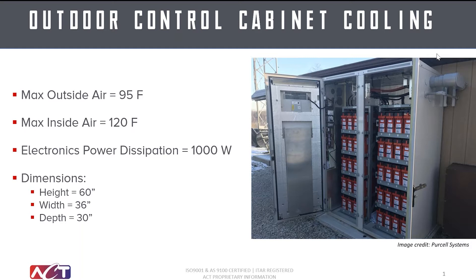The boundary conditions you see on the left are potential environmental requirements you might see from a customer, dictated by the components in your system and where the cabinet is being deployed. The max outside air temperature based on the climate is 95 degrees Fahrenheit. The max inside air temperature, mostly dictated by the survival temperatures of the electronics, is 120 degrees Fahrenheit. The waste heat or electronics power dissipation — found by summing all the data sheets from your components — is estimated at 1000 watts. The enclosure dimensions are 60 inches tall, 36 inches wide, and 30 inches deep.